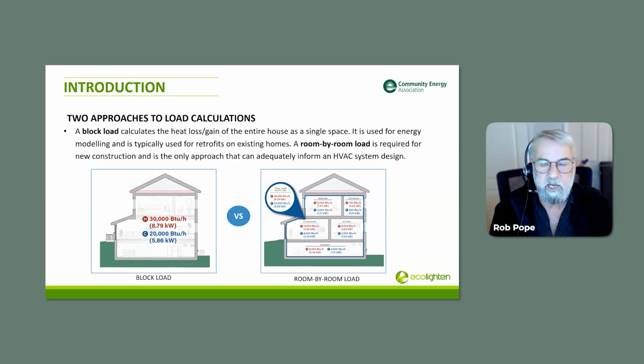You can't design a mechanical system without knowing where the loads are in each of the rooms. How much does the bedroom need? How much does the bathroom need? And so on, for cooling, for heating. So the block load is more for existing homes, not exclusively, and room by room is exclusively for new construction.